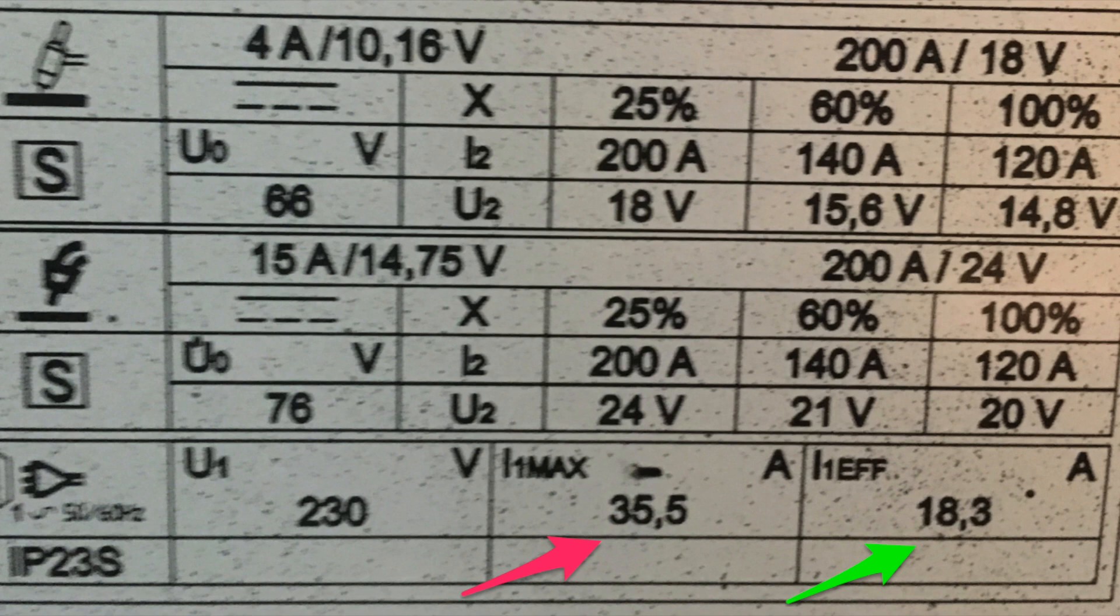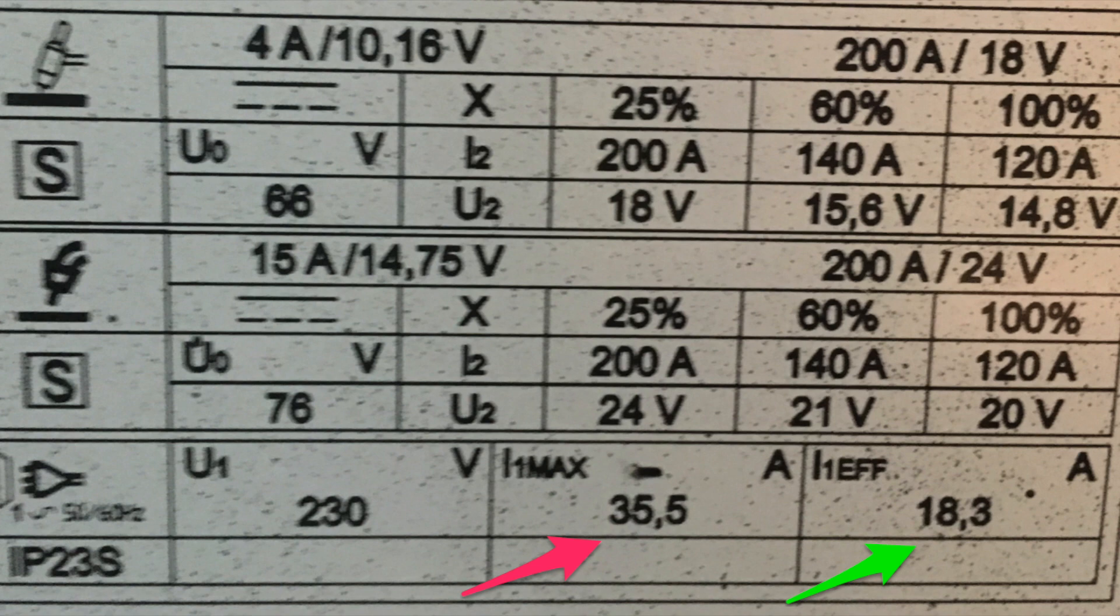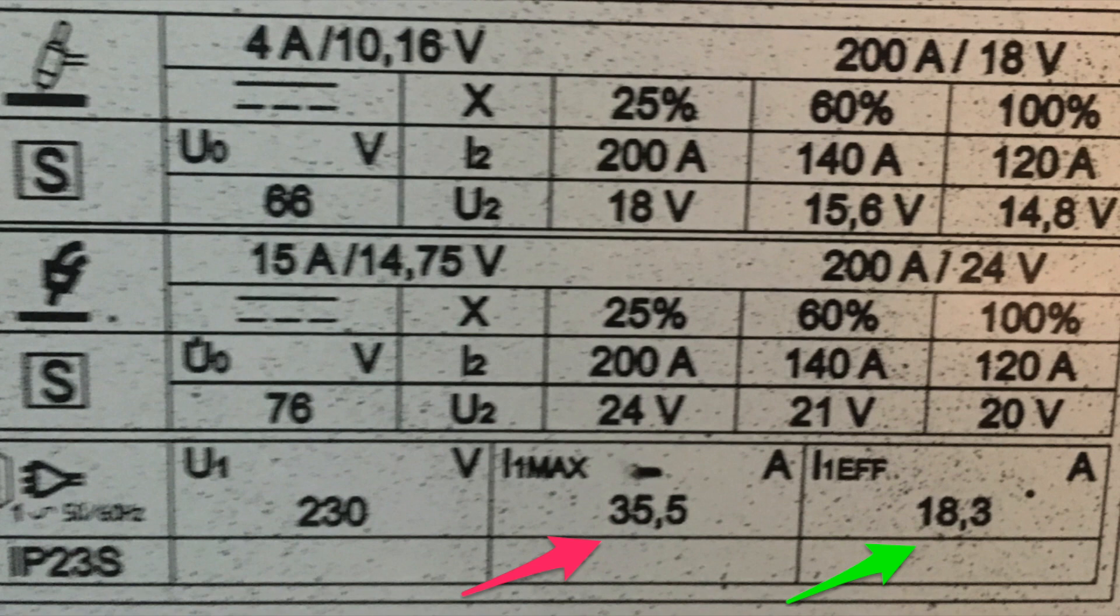The effective current draw is 18.3 amps, which the effective current draw also accounts for the duty cycle of the machine. As long as that is under 20 amps you are pretty much safe to run this machine on the 20 amp breaker. Of course under maximum load it will pop, but you can't be running maximum load on it in the first place. And if you would be running maximum load the machine would go into overheat eventually. So it's a good way to get you by in a pinch if all you have is a 220 volt machine and you want to use it on a 110 volt circuit.